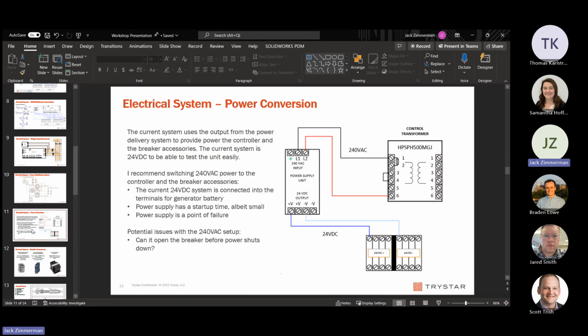Power conversion, this one's just unbelievably simple, but all we're doing from that 277 volt that we're getting off of those relays and those contactors is we're just converting it to 240 and then feeding it into a power supply to get to 24. We're using 24 volt DC power because I wanted to be able to safely, without energizing the unit with dangerous power, test the unit at every stage. Because 24 volt power is implicitly safe per OSHA.